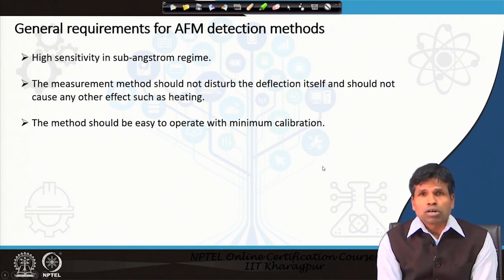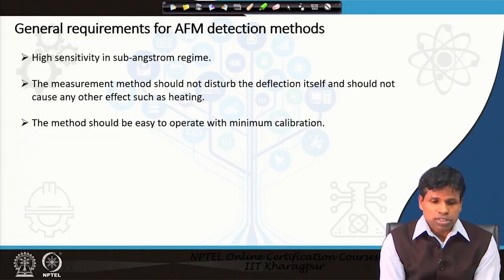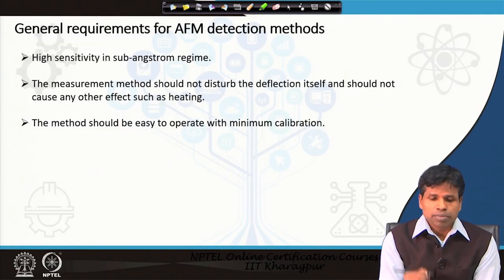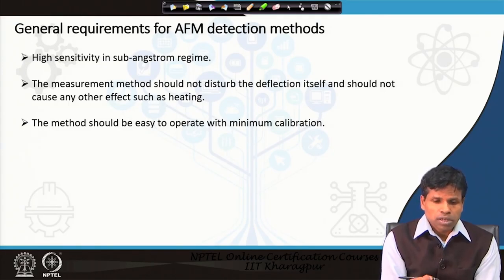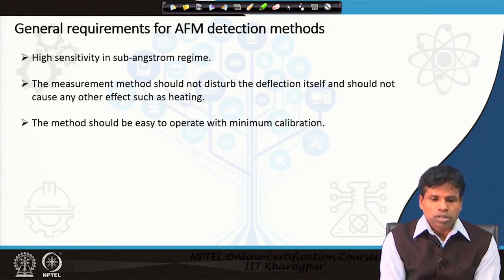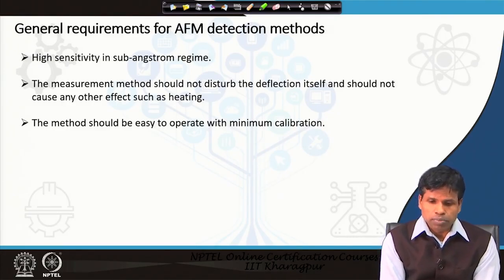The requirements for this detection method are that high sensitivity of the detection system is needed in the sub-angstrom region, because the height measured in AFM is normally below 1 angstrom. The deflection of the AFM cantilever is in the angstrom range, so the detection system should allow measurements in the sub-angstrom regime. Also, the measurement method should not disturb the deflection itself, should not cause any other effect such as heating, and should be easy to operate with minimum calibration.